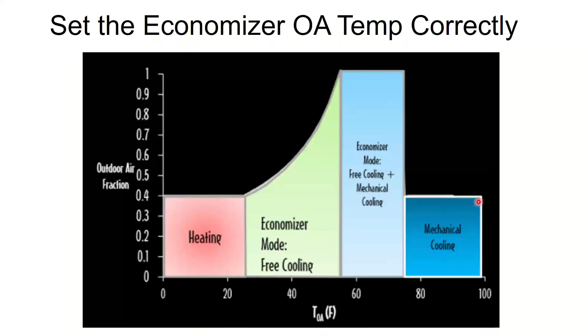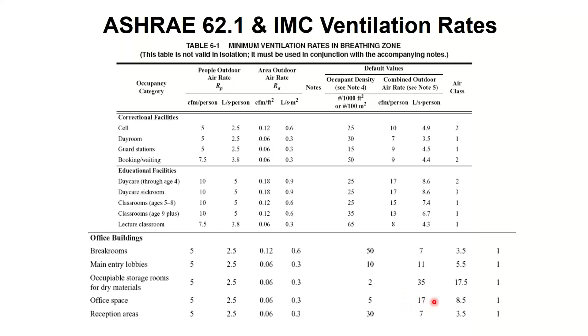I say approximately. This is an office building chart. I say approximately 17 because now it's divided, you've got to add these 2 things together. But if you take the typical occupancy, this density right here, and multiply it out, it comes out to about 17 CFM per person for an average density. But you don't do it by that anymore. In any case, most of the buildings that are out there now, when you rehab them and bring them up to the current codes, the ventilation rate is going to need to be higher.